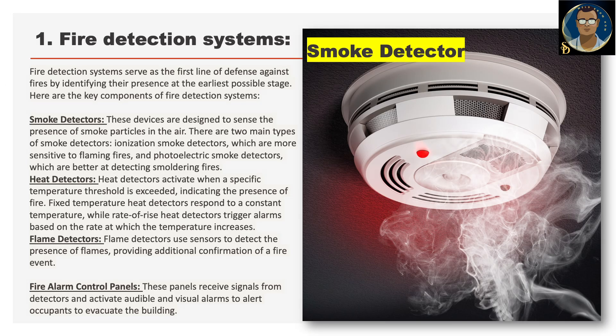The fire detection system serves as the first line of defense against fires by identifying their presence at the earliest possible stage. Key components include smoke detectors, heat detectors, flame detectors and fire alarm control panels. Smoke detectors sense the presence of smoke particles in the air. There are two main types: ionization smoke detectors, which are more sensitive to flaming fires, and photoelectric smoke detectors, which are better at detecting smoldering fires.